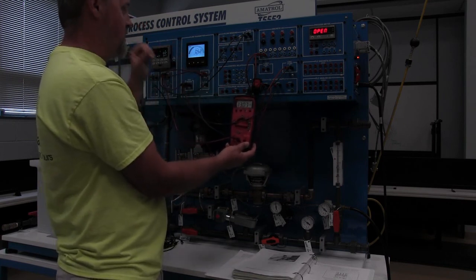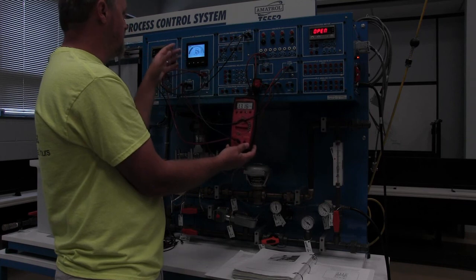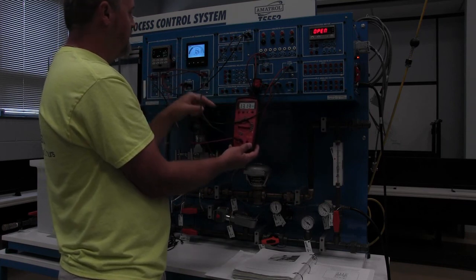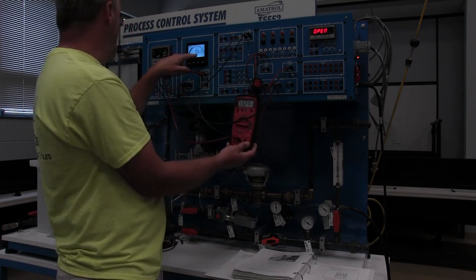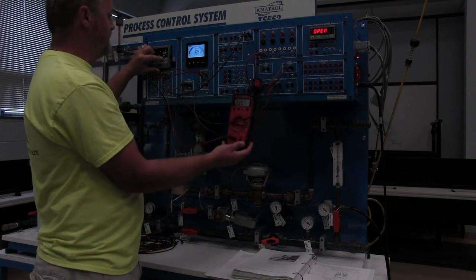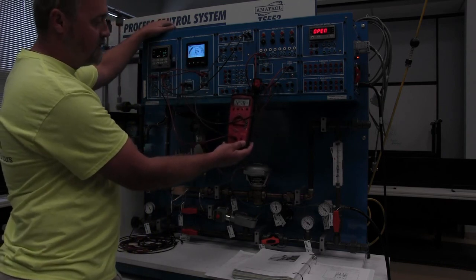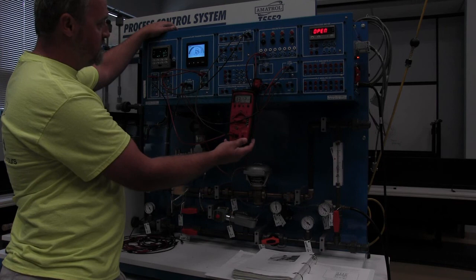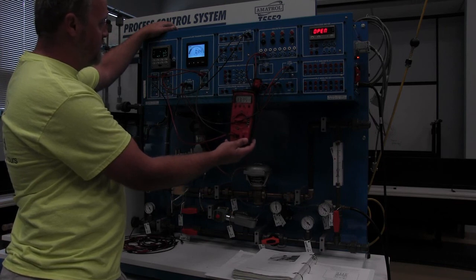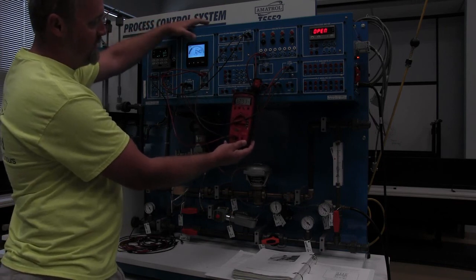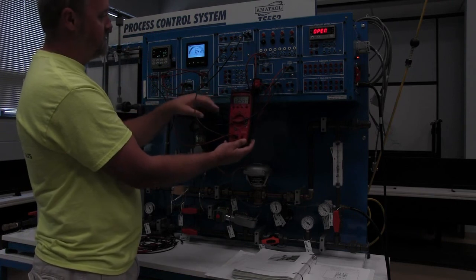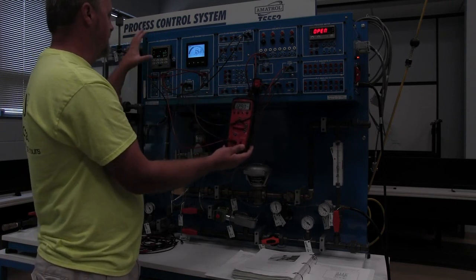to make sure it doesn't overshoot once it gets to its set point. So it's still closing a little bit because we're flowing a 0.51 and my set point is a 0.41. So it's just slowly closing, just trying to get it down to that 0.41. Now it's overshot a little bit, so you're going to see this milliamp signal decrease, trying to get there.